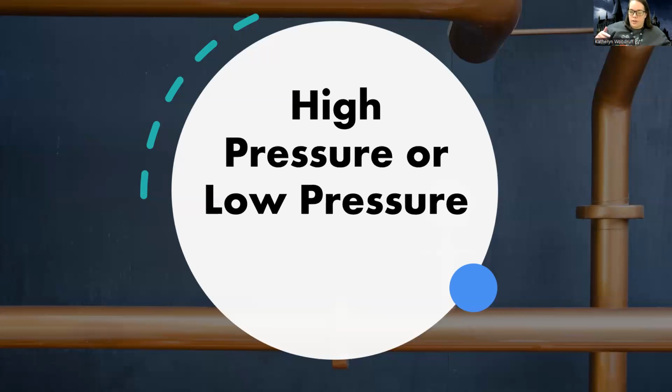In my other video that talks about alarms, I talk about how there's resistance because there's a kink in the tube, too many secretions, the patient's awake and agitated, or there's resistance in the lungs. So high pressure is resistance either in the tubing or in the person themselves. Something is making it harder to get the air, the oxygen, the flow pushed into this patient. If a patient is talking, imagine you're awake and trying to talk, you're creating more pressure from the patient's side, and that creates resistance for the ventilator to be able to do its job. So usually when a patient is talking, it's going to be a high pressure alarm.